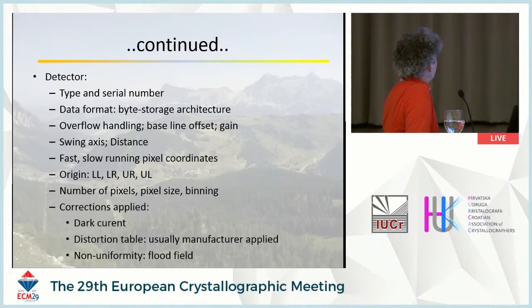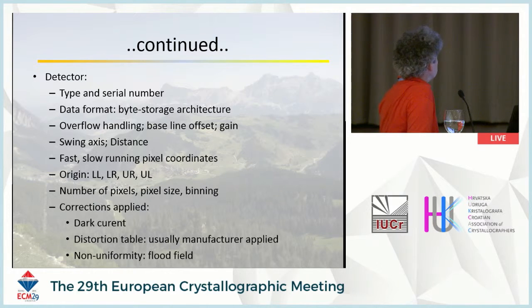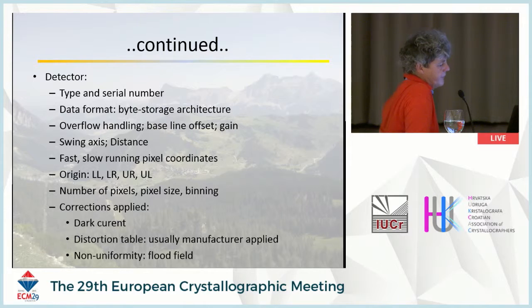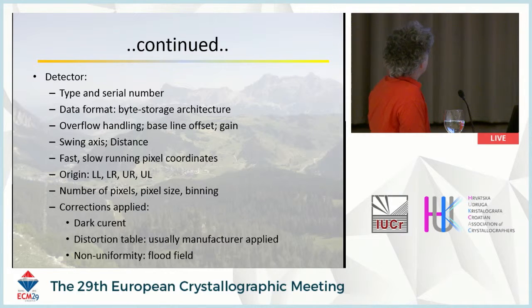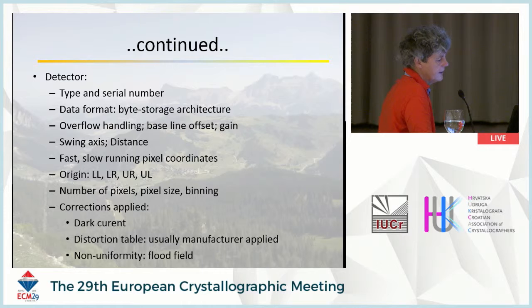For the detector, it would be very useful to have the type and serial number — maybe you can learn typical characteristics from that. The data format should specify the byte storage architecture, how to handle overflows, any baseline offset, the gain, detector-to-sample distance, swing axis, and critically, the pixel coordinate convention: which direction is horizontal or vertical, and where the origin is — lower left, lower right, upper right, or upper left.